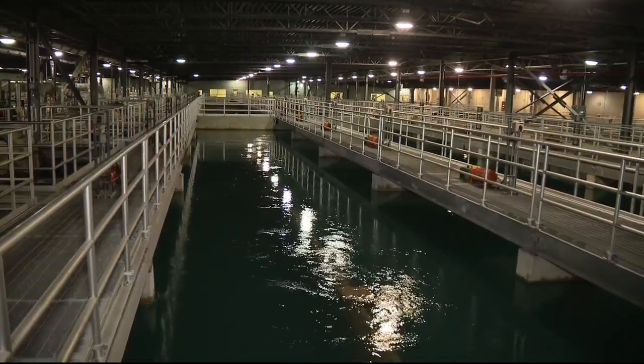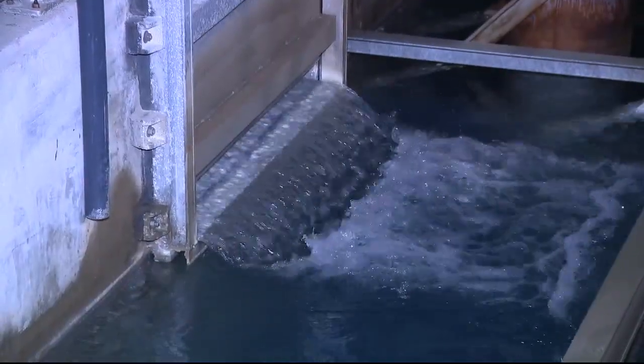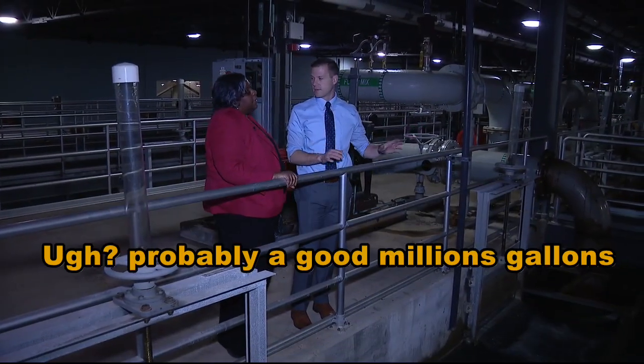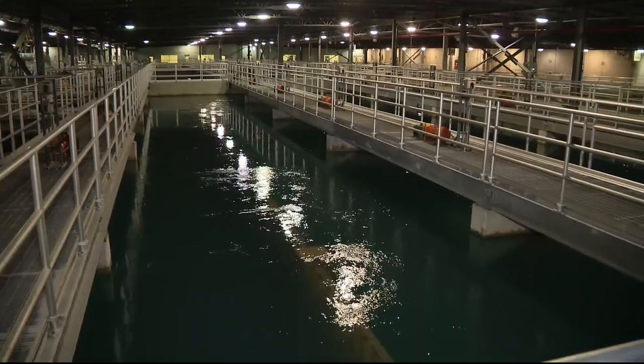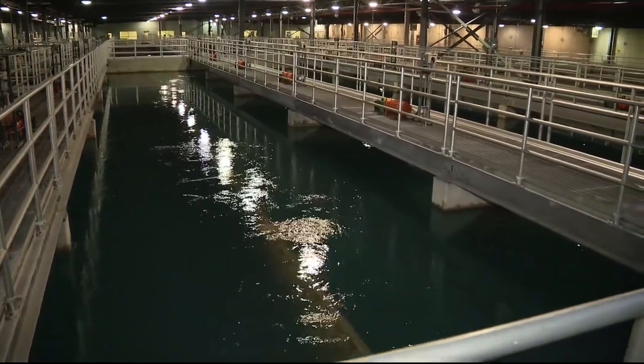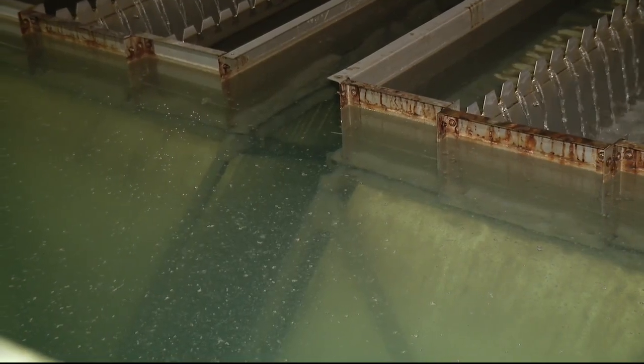The water then flows in here. It's quickly mixed, then slowly mixed with more chemicals. There's probably a good million gallons in here. It's churned by fans underwater — they actually look like large ceiling fans inside a basin. What you're looking at here is a process called flocculation, where any floating dirt clumps together. That's important because we're clumping that dirt together and we want it to stay together.